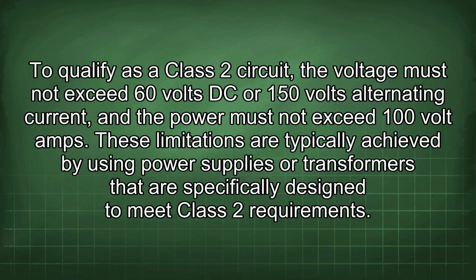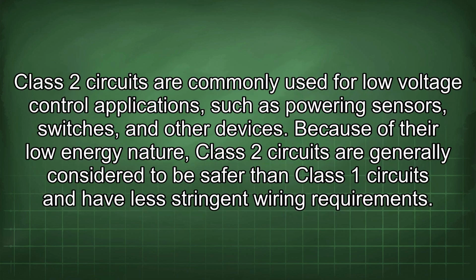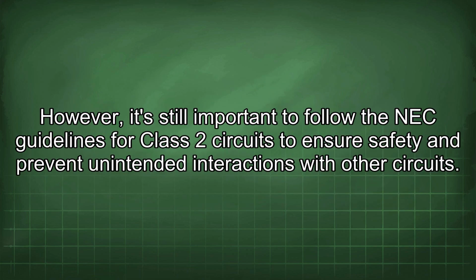These limitations are typically achieved by using power supplies or transformers that are specifically designed to meet Class 2 requirements. Class 2 circuits are commonly used for low-voltage control applications such as powering sensors, switches, and other devices. Because of their low-energy nature, Class 2 circuits are generally considered to be safer than Class 1 circuits and have less stringent wiring requirements. However, it's still important to follow the NEC guidelines for Class 2 circuits to ensure safety and prevent unintended interactions with other circuits.